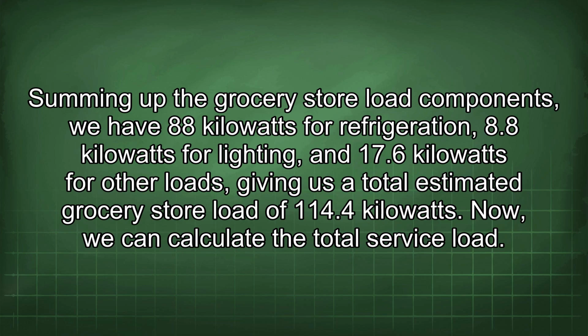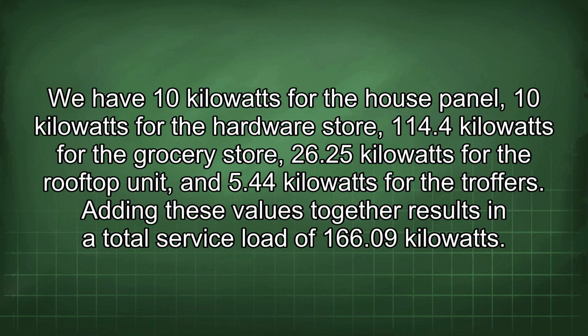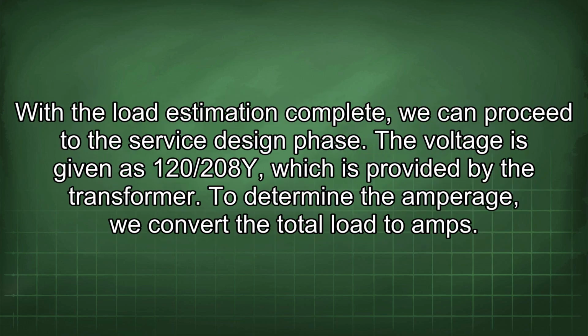Now, we can calculate the total service load. We have 10 kilowatts for the house panel, 10 kilowatts for the hardware store, 114.4 kilowatts for the grocery store, 26.25 kilowatts for the rooftop unit, and 5.44 kilowatts for the troffers. Adding these values together results in a total service load of 166.09 kilowatts. With the load estimation complete, we can proceed to the service design phase.